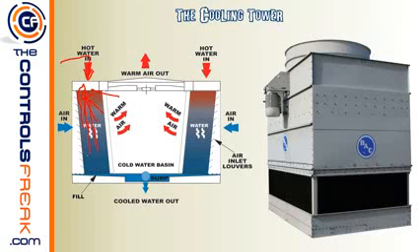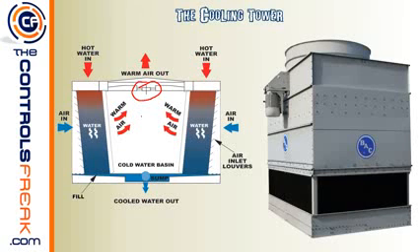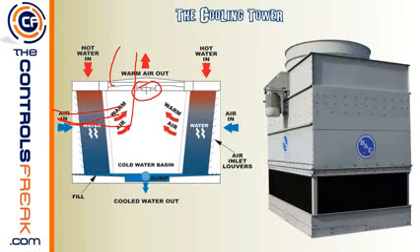The water raining down across the fill with natural air flow provides a first stage of cooling. A second stage — or sometimes the primary stage depending on the control sequence — is the fan. When the fan turns on, it pulls air in and shoots it out the top. As that air passes across the water, it helps cool it down.